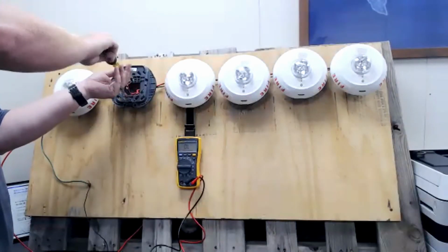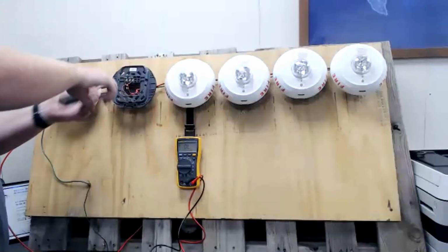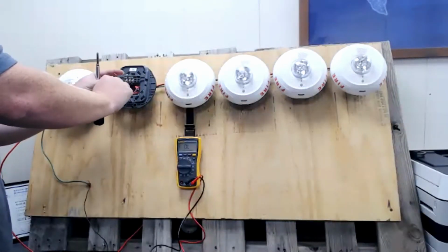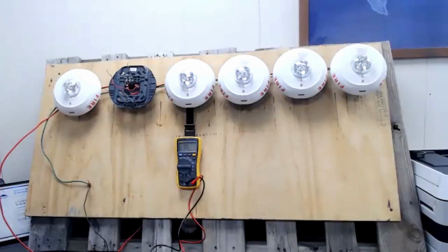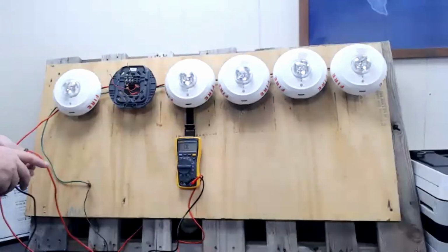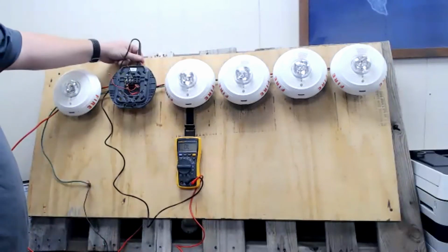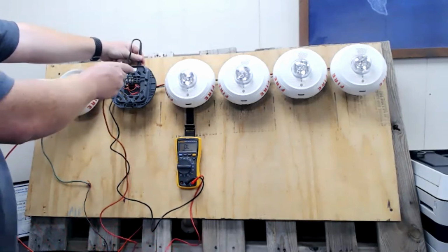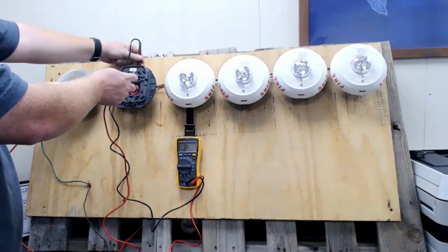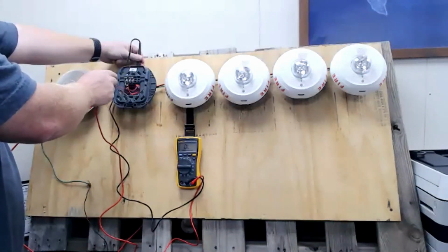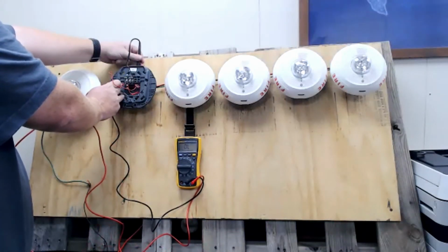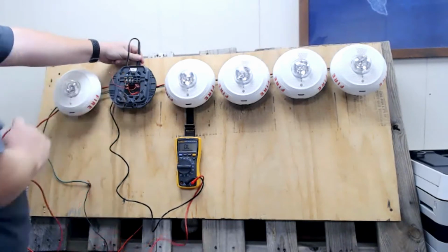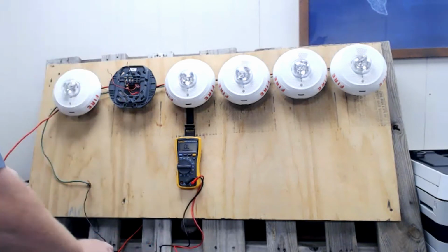All right, so I'm going to take that, and I'm going to go ahead and disconnect it so we can do like we did, checking for ground fault at the last one. Even though I know I did just find a ground fault, there might be more than one. So doing the same thing, I'm going to put my meter lead onto the ground reference, which in this case is our back boxes. Touch it right here. Completely open line. Here, completely open line. This one, open line. Right here, open line. So that tells me this was probably our only ground fault.